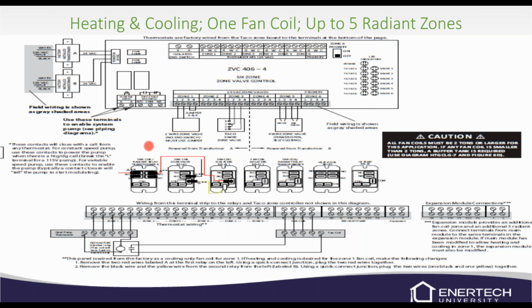Now on this, you can see you've got these little red lines. You will have to do a little bit of setup. If zone number 1 is going to be heating and cooling, we've got to make sure that this relay is switched over so that it knows that it's a heating and cooling zone. So make sure that we're definitely reading the wiring diagrams and looking at these notes and things so we can get it set up properly.